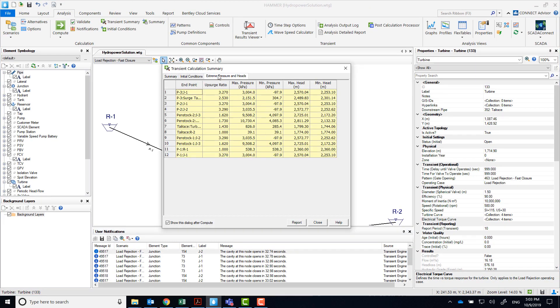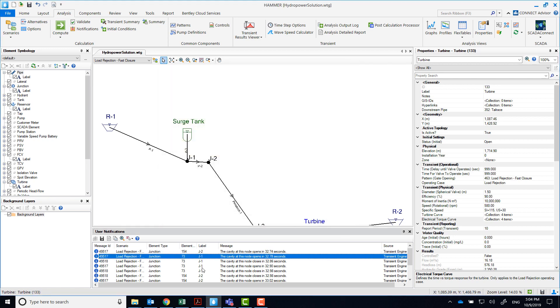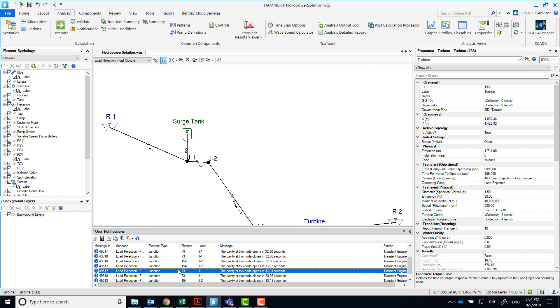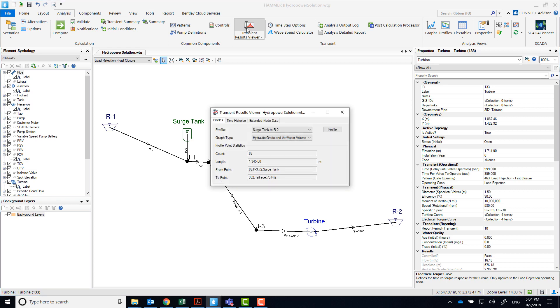Notice the max surge pressure and also the nodes that reached vapor pressure. Notice that there are many user notifications about cavities opening and closing at J1 and J2.